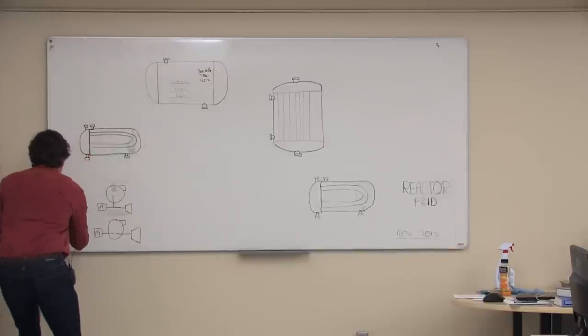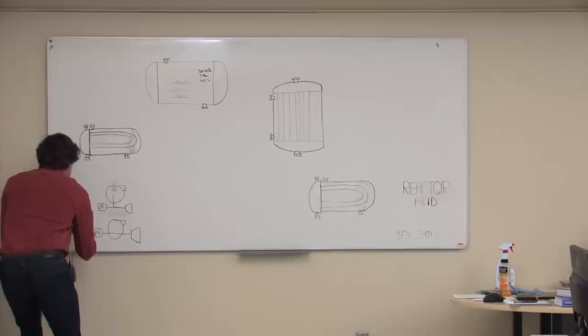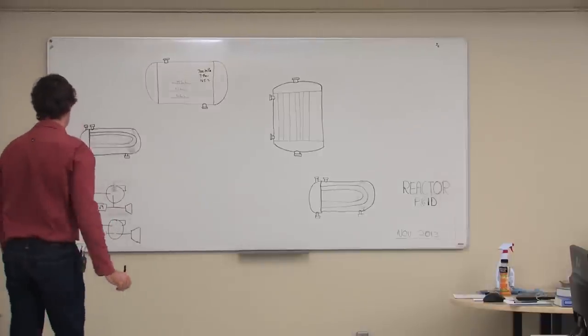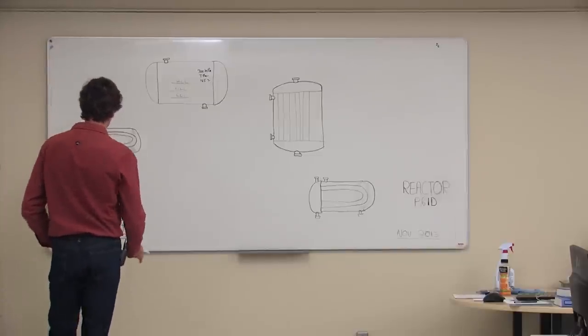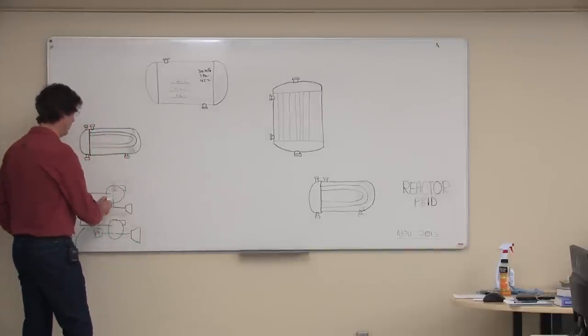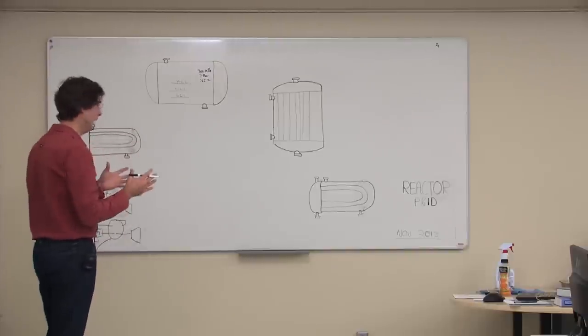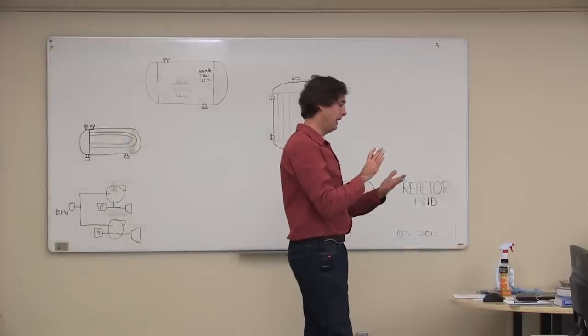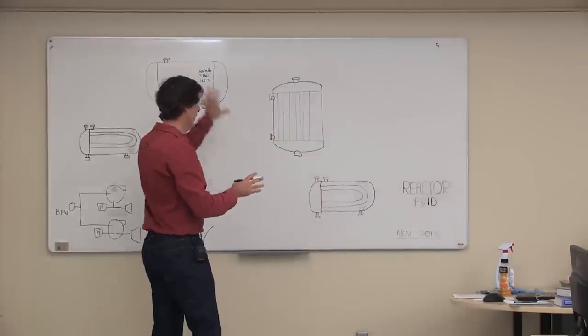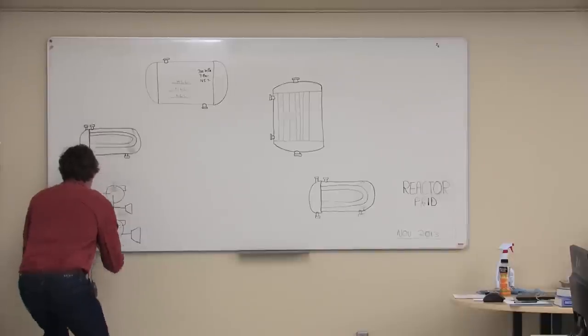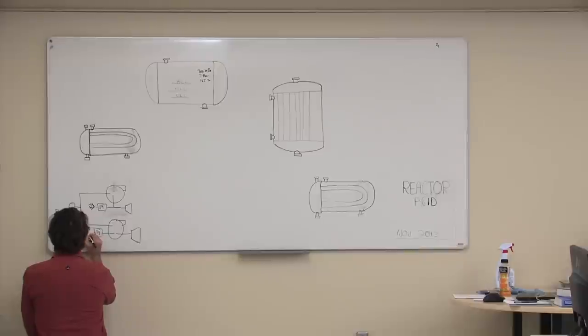We know we're going to have boiler feed water coming in the side of the drawing — it'll come in from a utility P&ID, so we don't need to show the drawing number yet. Now, these are special pumps because we're putting steam turbines on them, but in general when you put a pump and motor together, there's a standard envelope of stuff. My recommendation is to draw one on some graph paper, photocopy it, and move those around until you're happy with where they're placed. The standard controls include a motor control center shown with an interlock symbol.